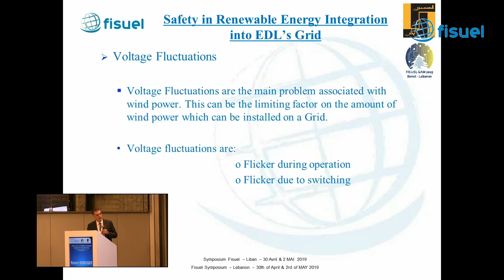For the safe integration of renewable energy, the influences on wind farm integration are mainly voltage fluctuations and harmonics. Voltage fluctuations are the main problem associated with wind power. This can be the limiting factor on the amount of wind power which can be installed on the grid. Voltage fluctuations can occur during operation and are due to switching. The allowable frequency limits are generally established by individual utilities.